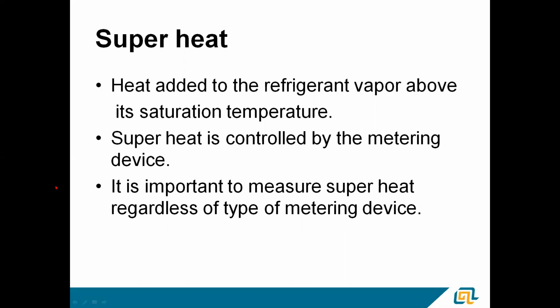So superheat is heat added to the refrigerant vapor above its saturation temperature. In other words, once it's in the evaporator, the temperature you're reading on your gauge, the pressure you're reading on your gauge, that's the saturated condition. With using a thermometer on the suction line, you'll be able to actually see what the superheat is. And superheat is extremely important. Superheat is controlled by the metering device, whatever type of metering device it might happen to be. And we're going to cover a couple of them in a minute.